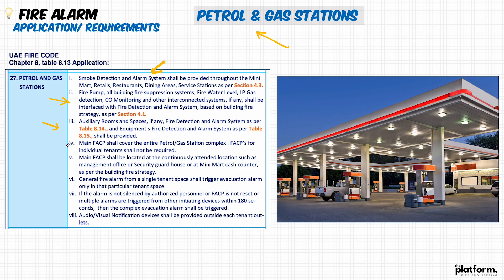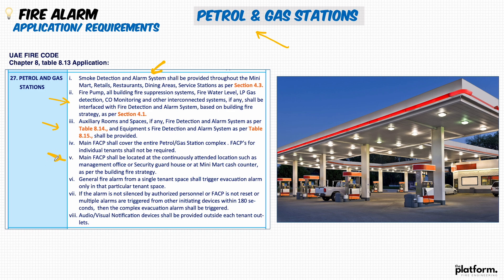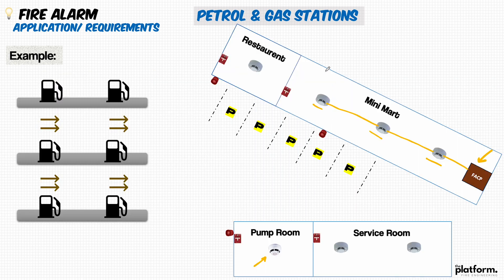The main controller shall cover the entire petrol station, so individual fire alarm control panels for each tenant area are not required. We don't need a separate fire alarm control panel for the restaurant or each individual area — a master panel or one main controller can control all areas via a fire alarm loop covering the entire station. The panel location shall be in an attended location like the management office or security guard house. A general fire alarm from a single tenant space shall trigger evacuation alarm only in that particular tenant space, without affecting the other retails.